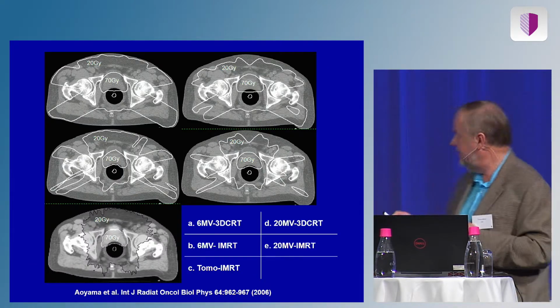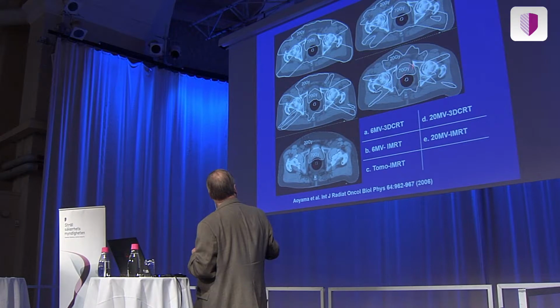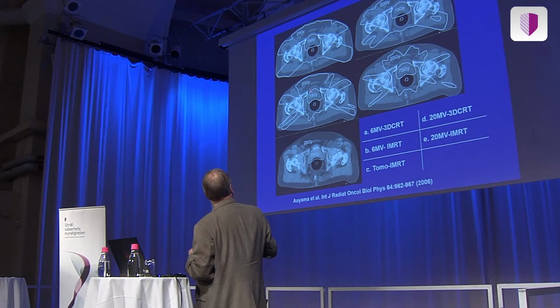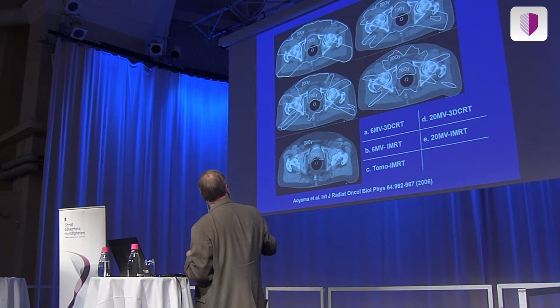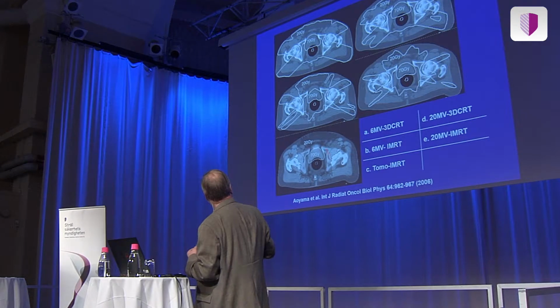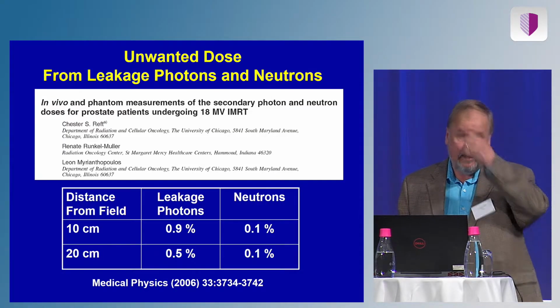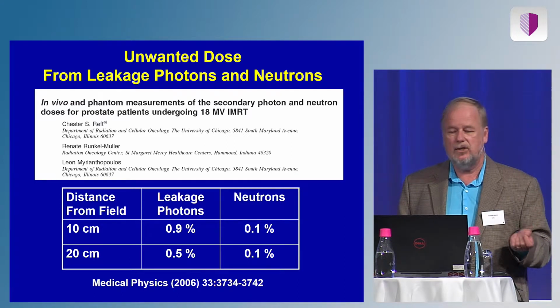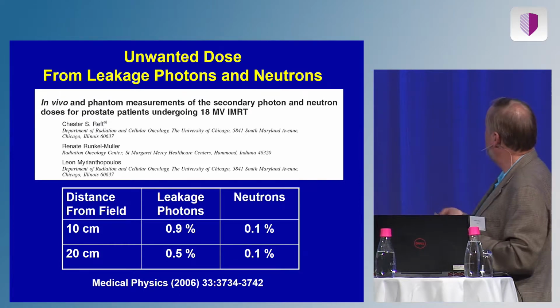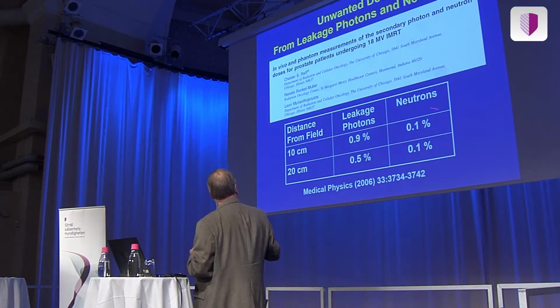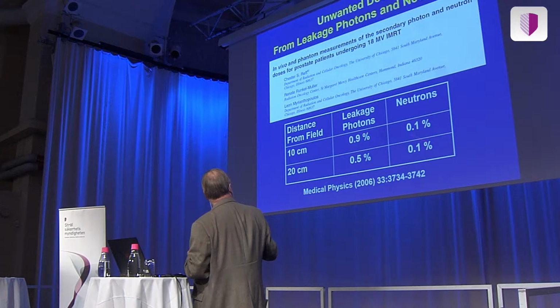And then tomotherapy is another example. So here are the 5 examples. This happens to be the 3D conformal. This is the 6 MV IMRT. This is the 20 MV 3D conformal, the 20 MV IMRT, and the tomotherapy or rotational therapy is much different. It has a much different kind of look. So the other thing you have to factor in to the total unwanted dose is the leakage photons, as I mentioned, and the neutrons. And it's going to depend on how far you are away from the field. This is the leakage photons at 10 centimeters away from a field, and the neutron dose, and at 20 centimeters and the neutron dose.